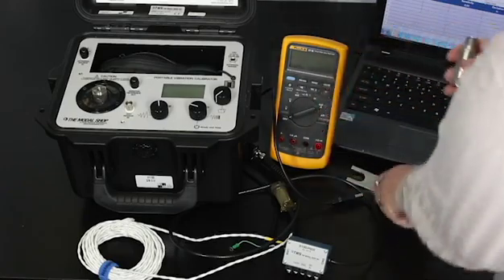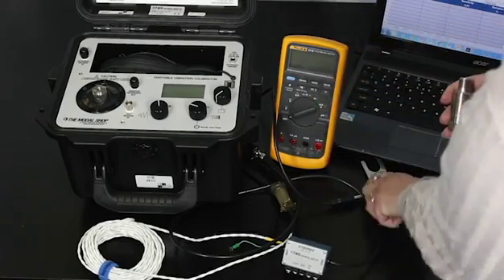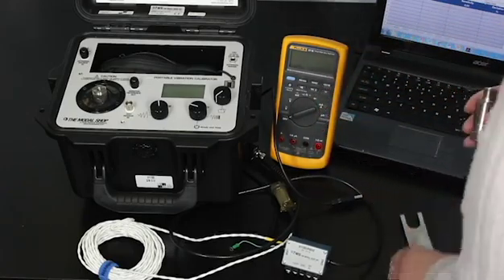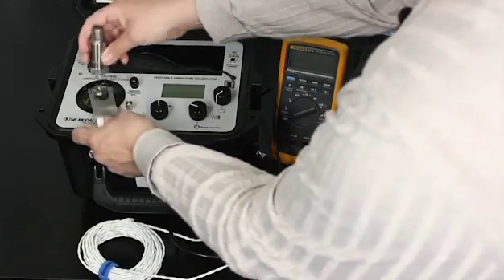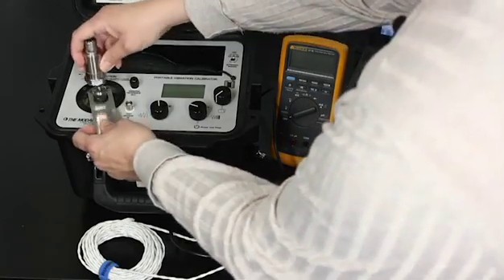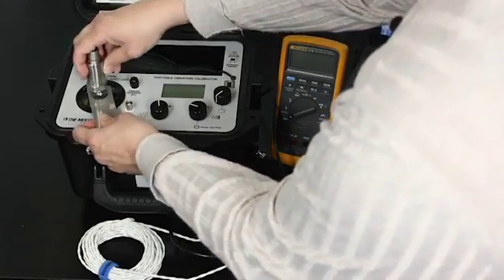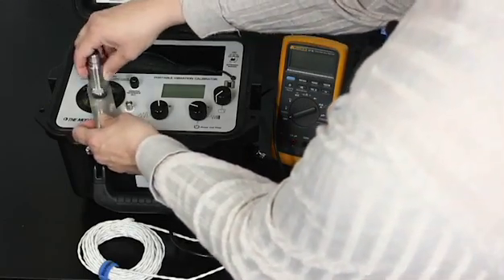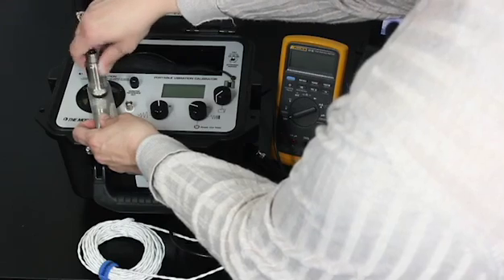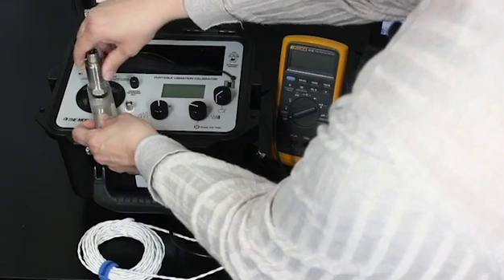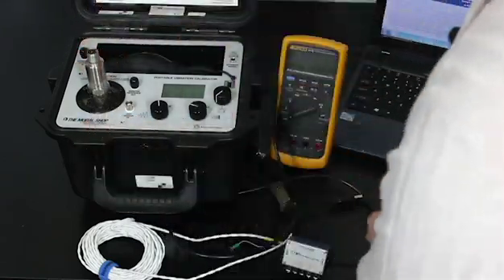First we need to mount our 4 to 20 milliamp sensor to the armature of the portable vibration calibrator. We do that with a mounting stud, and I'll just hand tighten it.